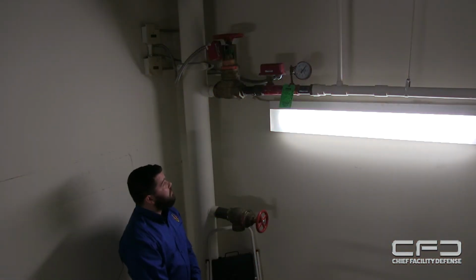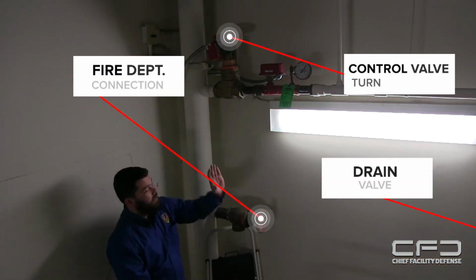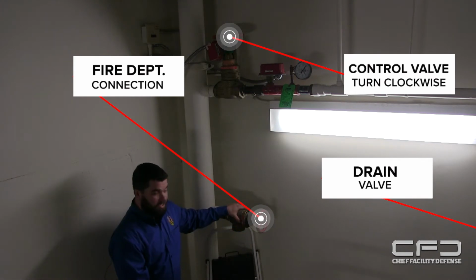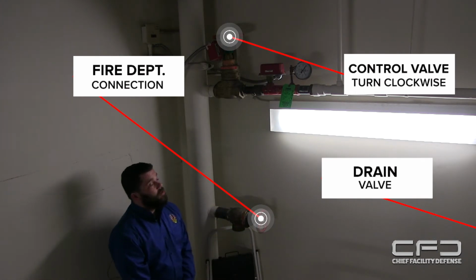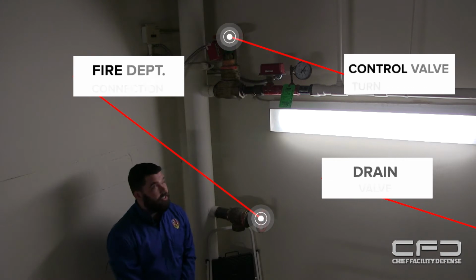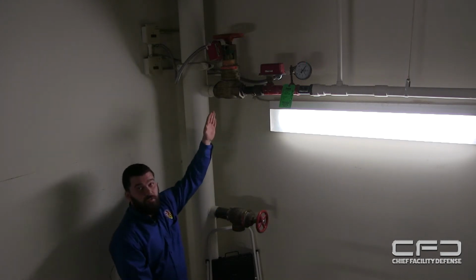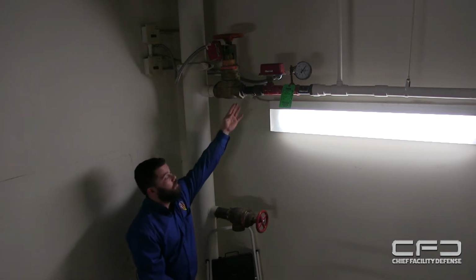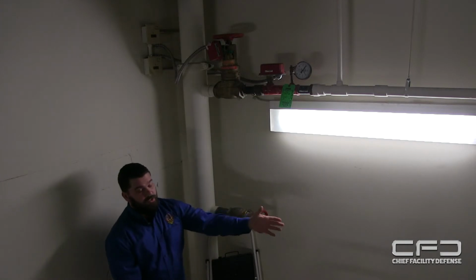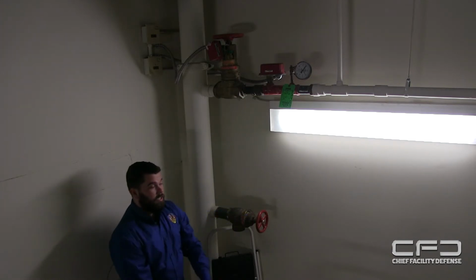On each floor in the stairwells, you're going to have a control valve and a drain and a fire department connection. In the case that a head ever goes off in a non-emergency situation, you want to immediately close the water supply valve right here, and they're all labeled, and open up the drain to drain all the excess water to protect the rest of the building.